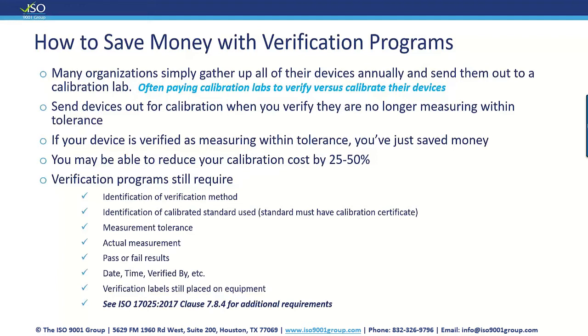Did it need to be calibrated? Well, let's go back. We said it only needed to be calibrated if it was not reading properly. But at minimum, you need to have a verification label on it. And you can see all of these additional requirements that are required on a calibration certificate in 17025, which is the standard that a calibration lab would use if they were calibrating your equipment. You can go purchase that standard. Look at clause 7.8.4, and you can list all of those things on your verification document.